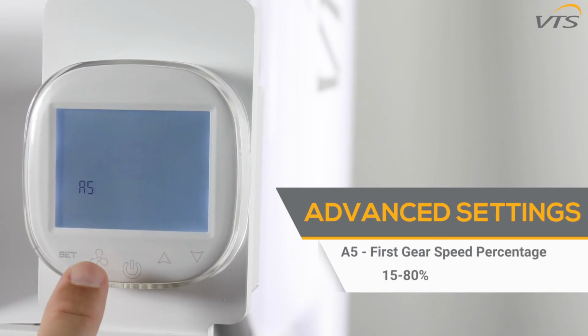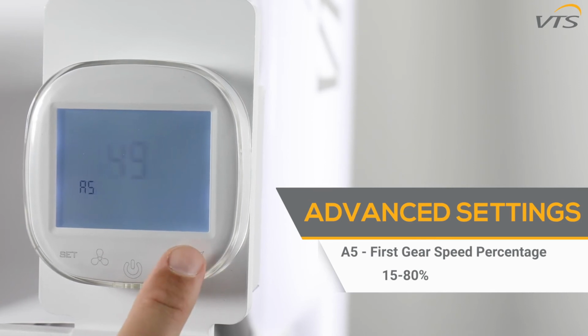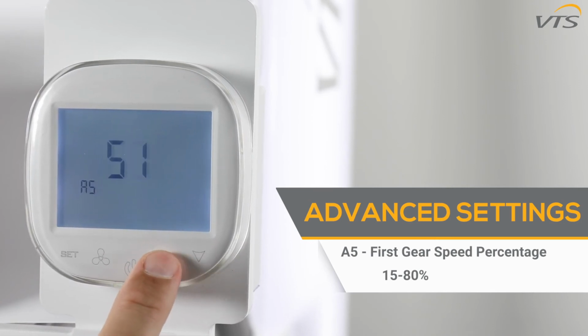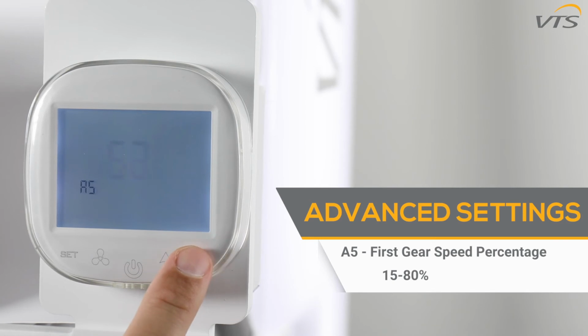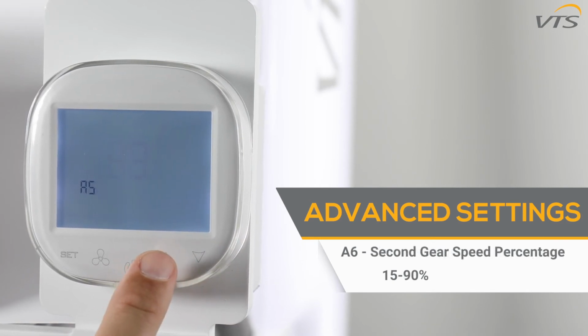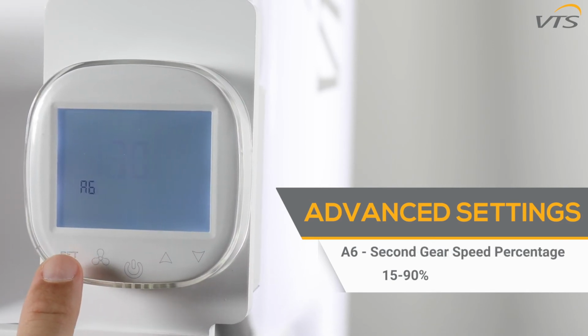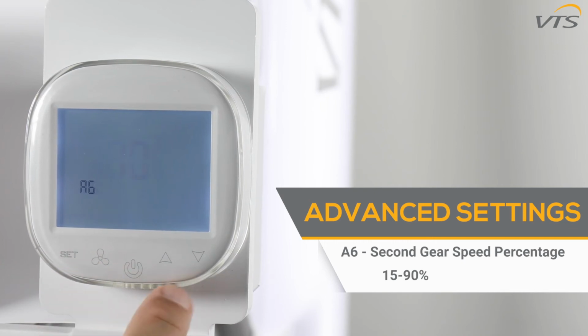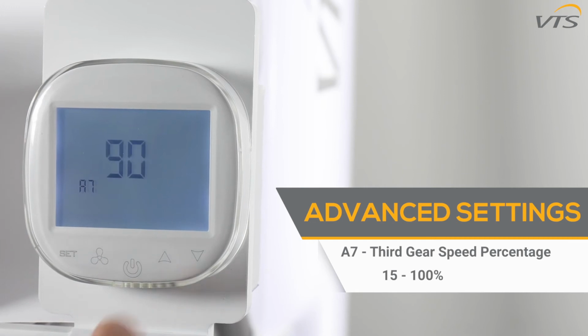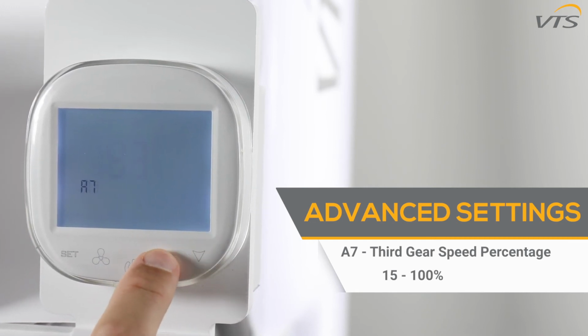The A5 function allows you to program the speed value for the first gear. Select a value from 15 to 80%. The A6 function allows you to program the speed value for the second gear. Select a value from 15 to 90%. The A7 function allows you to program the speed value for the third gear. Select a value from 15 to 100%.